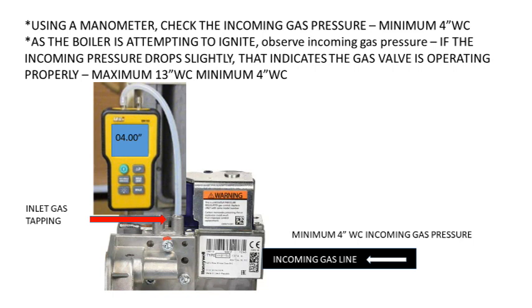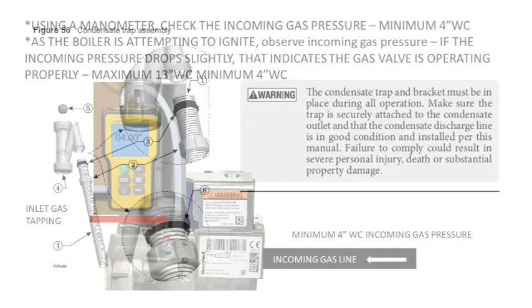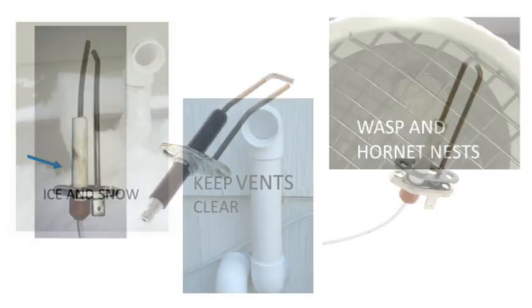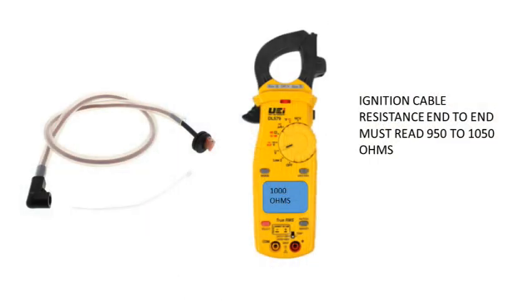Maximum 13-inch water column, minimum 4-inch water column. Is the condensate trap free flowing? Disassemble the condensate trap, clean and reassemble. Is the igniter worn or warped? Visually inspect the igniter. Is the exhaust or intake blocked in any way? Is the ignition cable resistance correct? It must read 1000 ohms plus or minus 50.